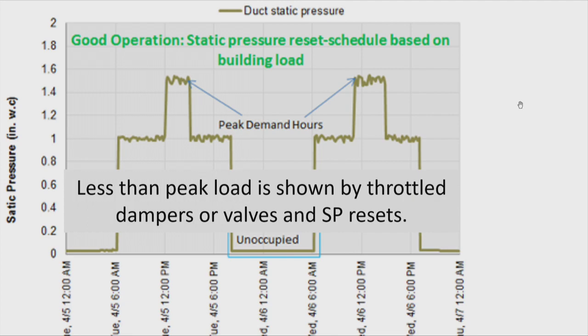But we can also reset based on dependent variables, that is, based on system variables. So we see that the dampers, or the valves, are moving a certain way. It indicates that we're at peak load, and therefore we can ramp up. When the valves throttle too much, we see that we're at a lower load, and we can ramp down.